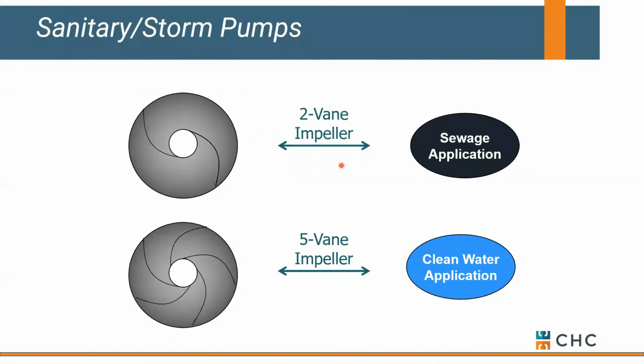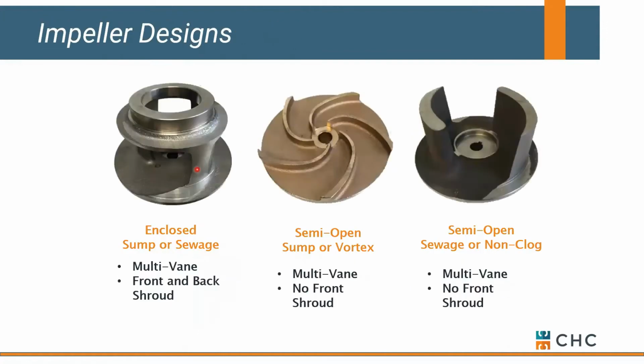So a couple things. If we're dealing with clean water, which we might call storm water or rainwater runoff, groundwater, anything that doesn't have a lot of solid in it, you typically have an impeller that has multiple vanes designed to pass clean water, not a lot of solid or particulate. If we're dealing with sanitary or sewage, you're going to find most of those have a 2-vane impeller, and the fact that we can pass pretty good solids or particulates through that style pump. That's really the only difference when you look at impeller sizes or impeller configurations.